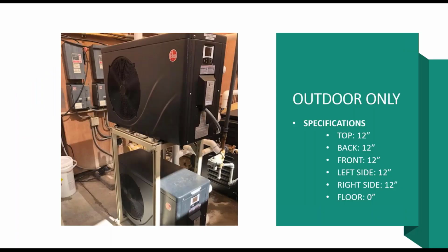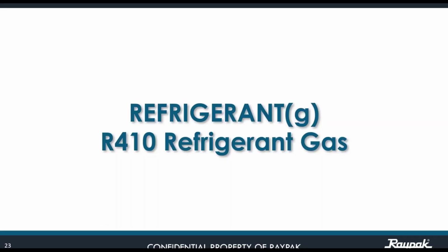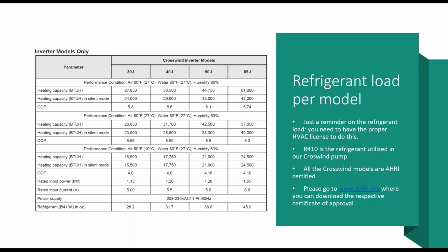Also, outdoor clearance, as I mentioned, is 12 inches on top, back, front, left side, and right side. On the floor, yes, you can put it on the floor. It's not going to be any problem. Regarding the refrigerant gas, it's R410A. And as I mentioned before, you need to have the proper license to do so.